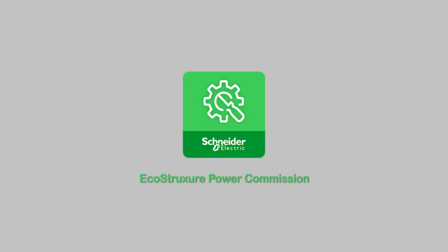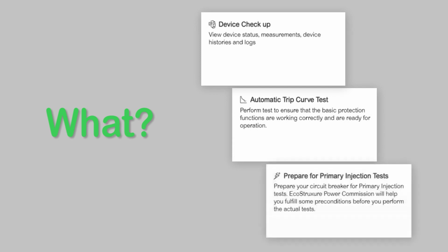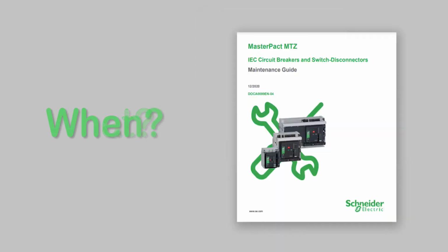EcoStruxure Power Commission offers 3 levels of breaker test. First, a quick and basic routine checkup. Second, an automatic trip curve test, which is equivalent to the secondary injection test. And third, one to prepare the breaker for more sophisticated primary injection test. Circuit breaker testing is recommended at both startup and every 2 to 3 years after that for preventive maintenance purpose.